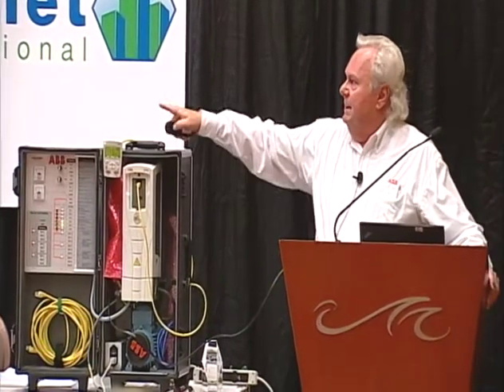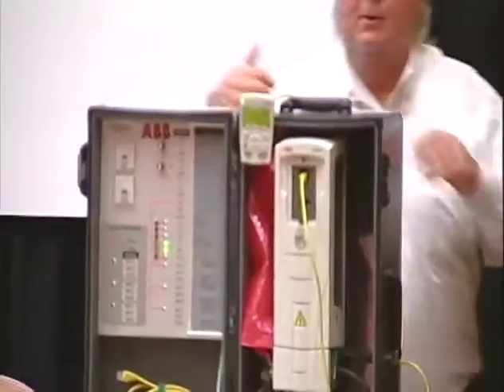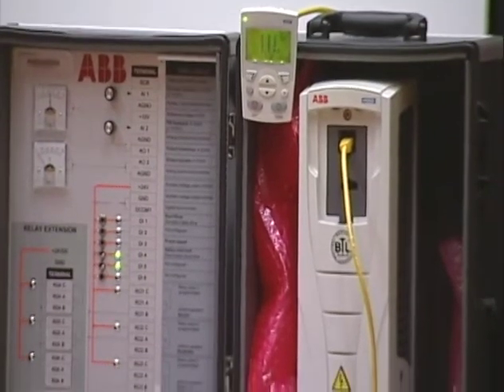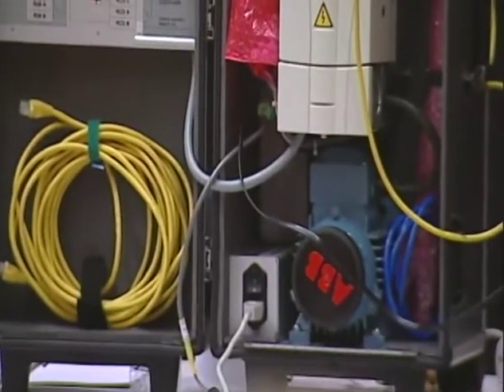They're there. So in this scenario, the hot water sensor is wired back to the energy management system box, the EMS box, and that is doing the PID loop, and then they're commanding the drive's analog output to control that hot water valve. So I need some hot water, I command the drive over BACnet, I see 20 milliamps, and the analog output goes to 20 milliamps. And for those of you in the front, you can see these meters on the demo cases going up and down. So I need 50%, I go 12 milliamps, okay? So I can output to whatever controlled device requires a 4 to 20 milliamp signal. I've got a free one sitting there.